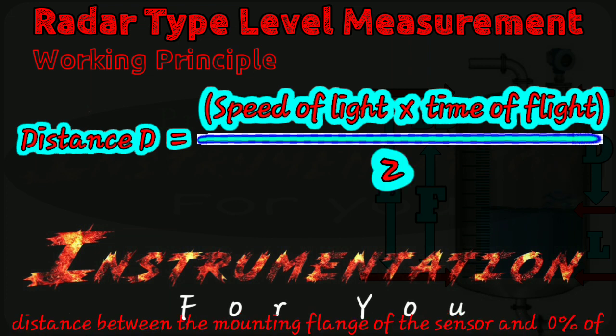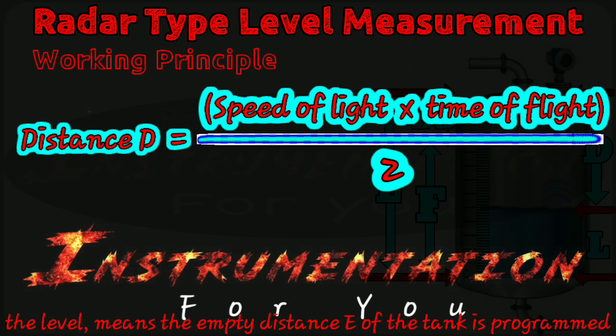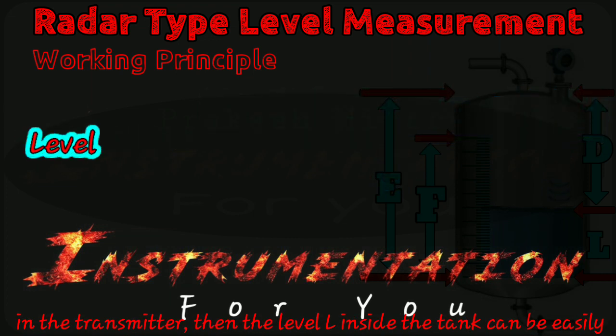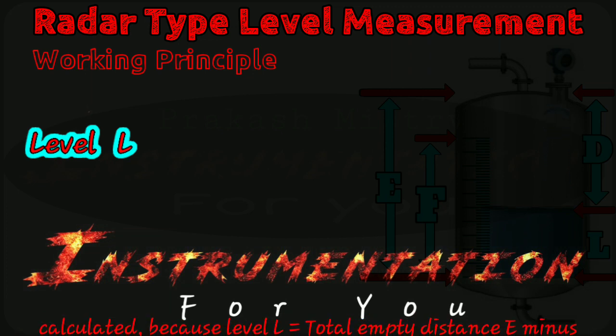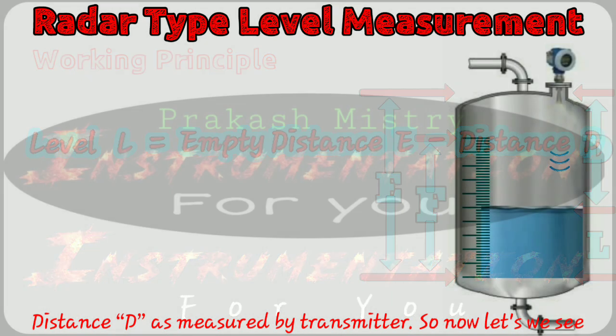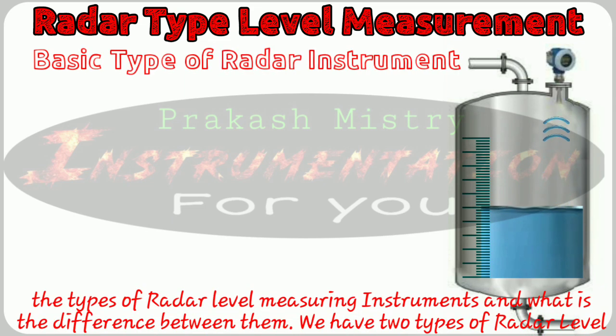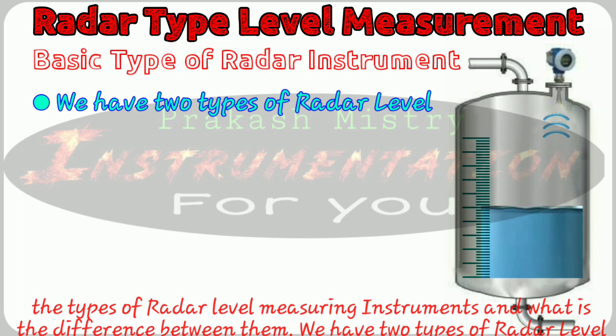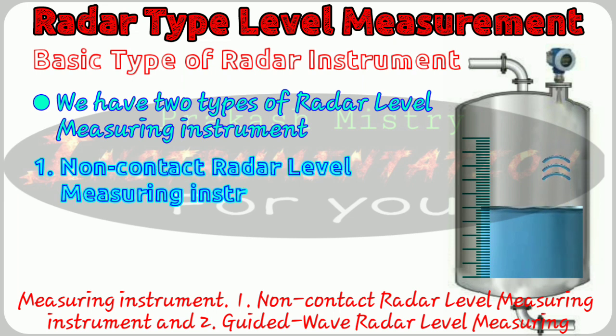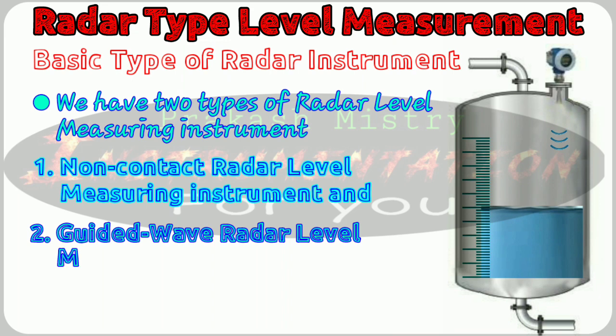If the total empty distance E between the mounting flange of the sensor and the 0% level of the tank is programmed in the transmitter, then the level L inside the tank can be easily calculated, because L equals total empty distance E minus distance D as measured by the transmitter. Now let's see the types of radar level measuring instruments and the differences between them. We have two types: non-contact type radar level measuring instrument, and guided wave radar level measuring instrument.